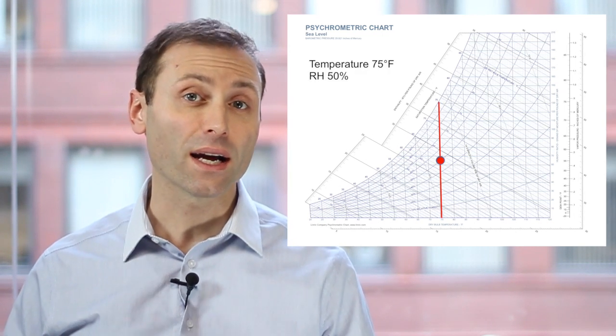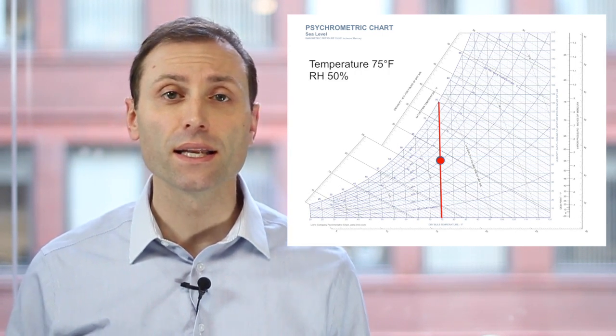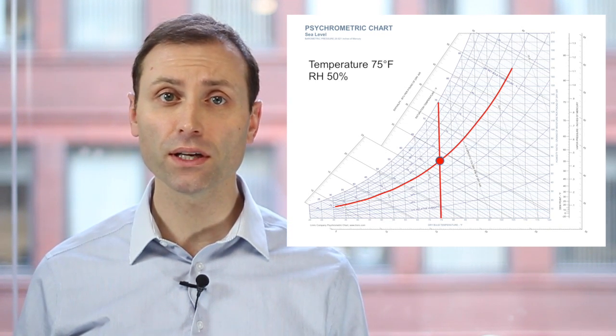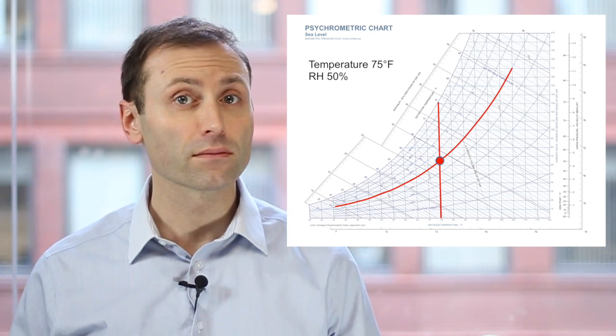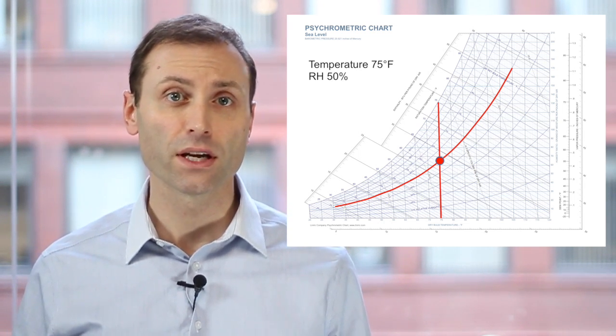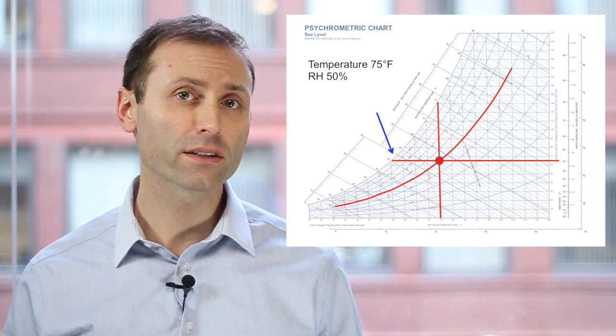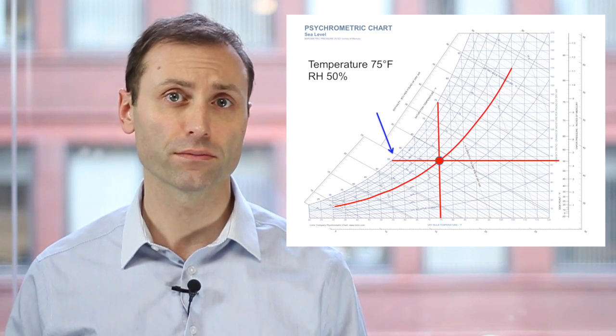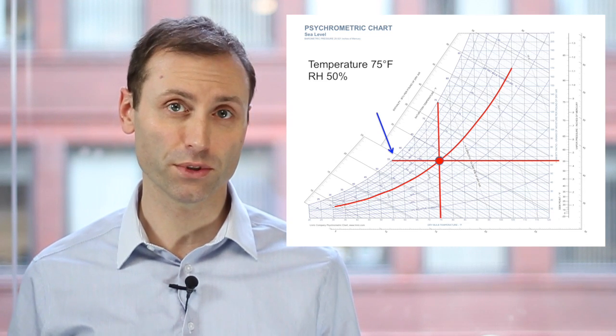Once you have one, I like to draw a thick vertical line through my temperature. Next, I draw a thick line through my relative humidity, which is represented by curved lines on the chart. I see where these two lines intersect and I draw a dot. Then I draw a horizontal line through the dot and see where it intersects with the left side of the chart, which is called the saturation curve. I read the number on the saturation curve to get my dew point temperature.